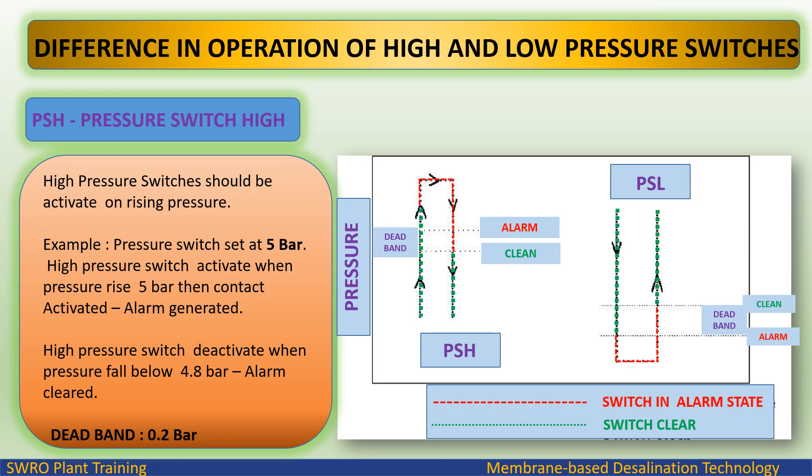Difference in operation of high and low pressure switches. High pressure switches should activate on rising pressure. Example: pressure switch set at 5 bar — when pressure rises to 5 bar, the contact is activated and an alarm is generated. The high pressure switch deactivates when pressure falls below 4.8 bar and the alarm is cleared. Dead band: 0.2 bar.